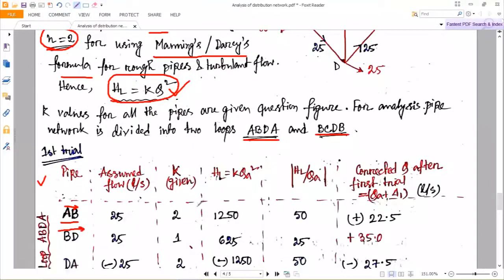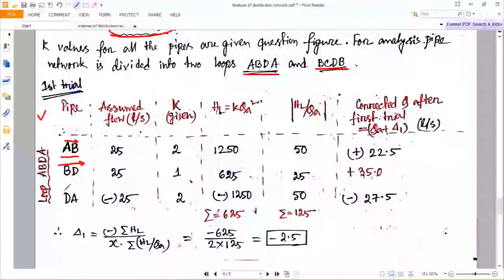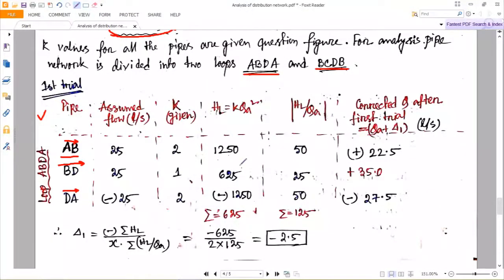The k values given are 2, 1, and 2. Now calculate h_L = k × Q_a^2. In the calculation of h_L, do not treat the negative sign as algebraically squaring — the negative is related to direction, not the magnitude. Head loss has a direction: if head loss from left to right is positive, then head loss from right to left will be negative. So you must indicate the head loss values with their positive or negative sign accordingly.